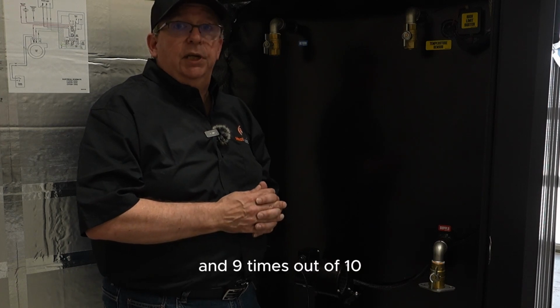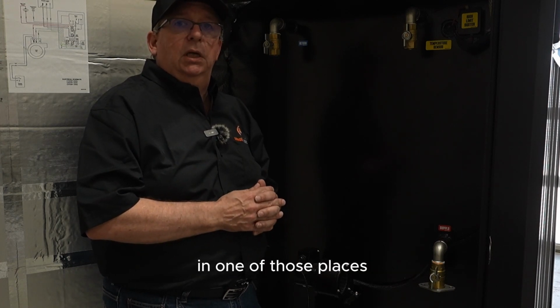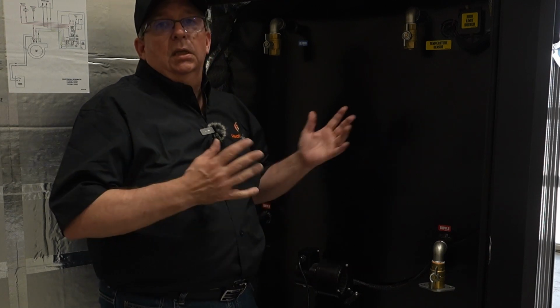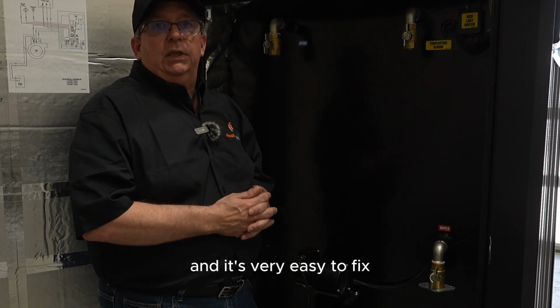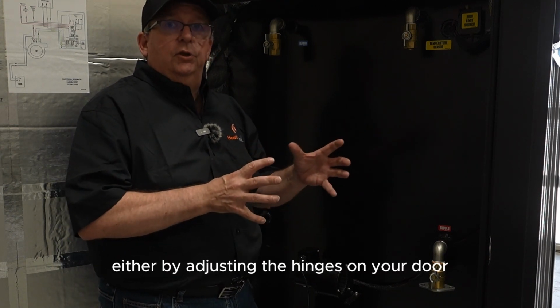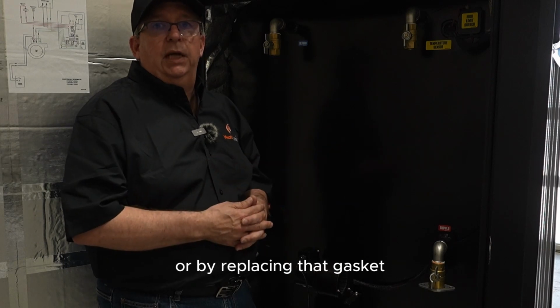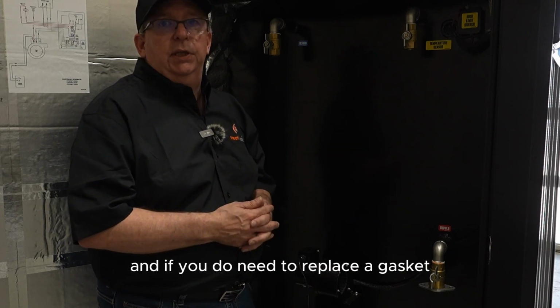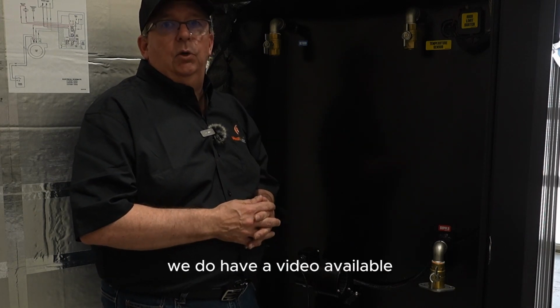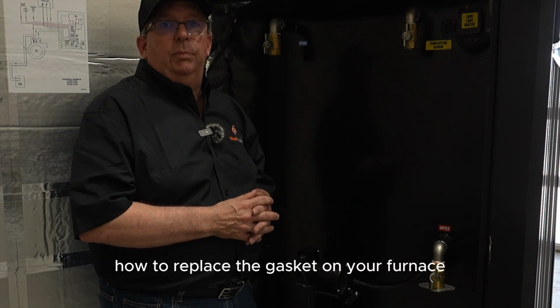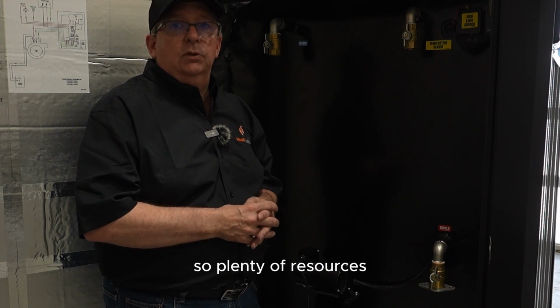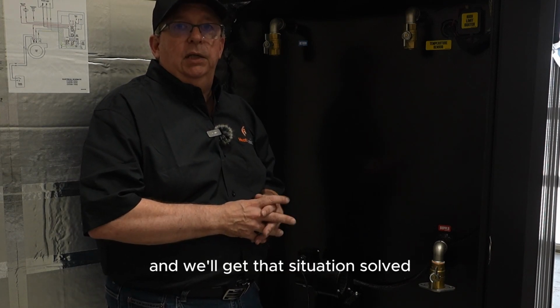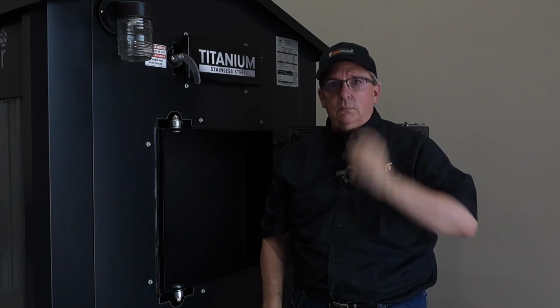And 9 times out of 10, you're going to have a small little leak in one of those places, and it's very easy to fix, either by adjusting the hinges on your door or by replacing that gasket. And if you do need to replace a gasket, we do have a video available on how to replace the gasket on your furnace. So plenty of resources, and we'll get that situation solved.